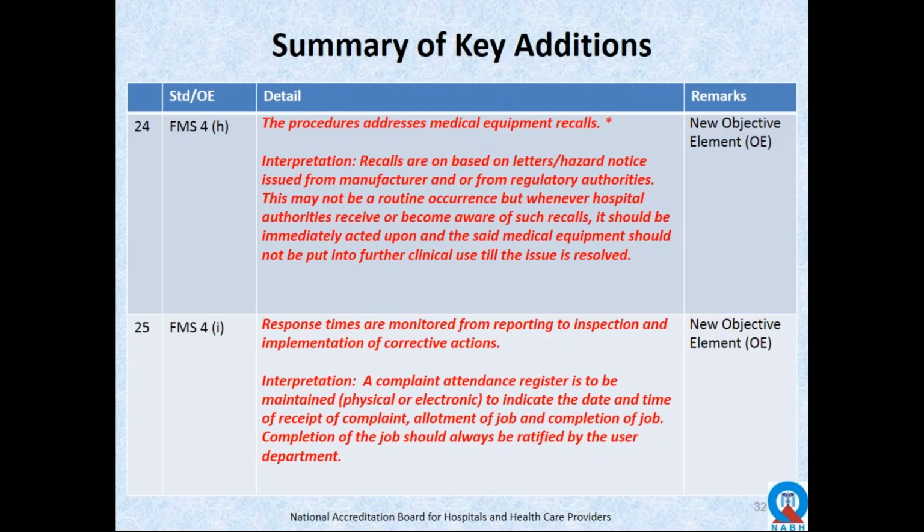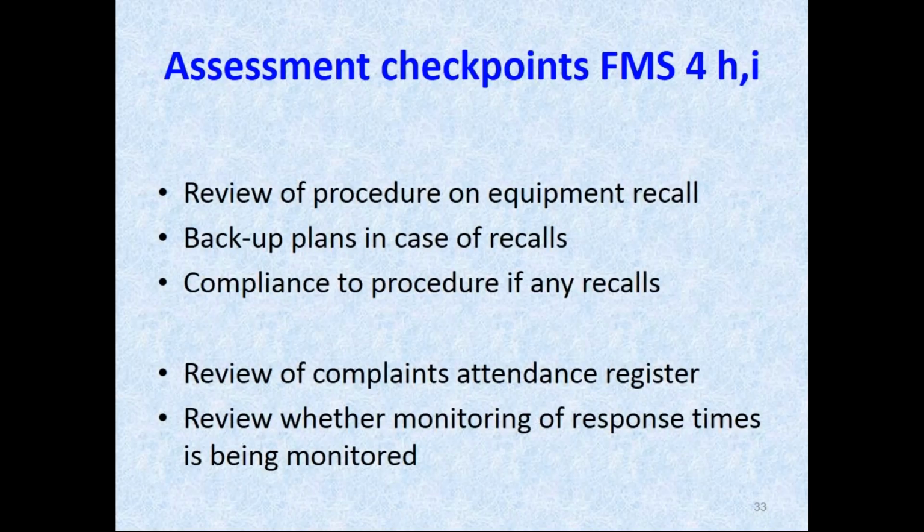Assessment checkpoints for FMS 4H and 4I: FMS 4H is related to the medical equipment recall, and FMS 4I related to the response times monitoring. So for the medical equipment recalls, we need to look at having a procedure for equipment recalls. We need to look into whether there are any backup plans in case a particular equipment has to be recalled as per the regulatory authorities' notification, whether any backup plan has been made for any backup equipment, and what is the compliance to the laid down procedure in case any recall occurs.